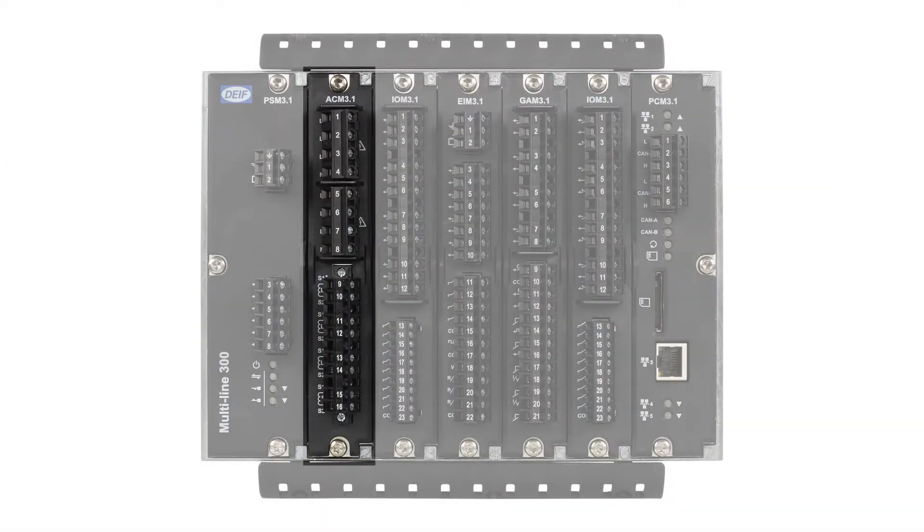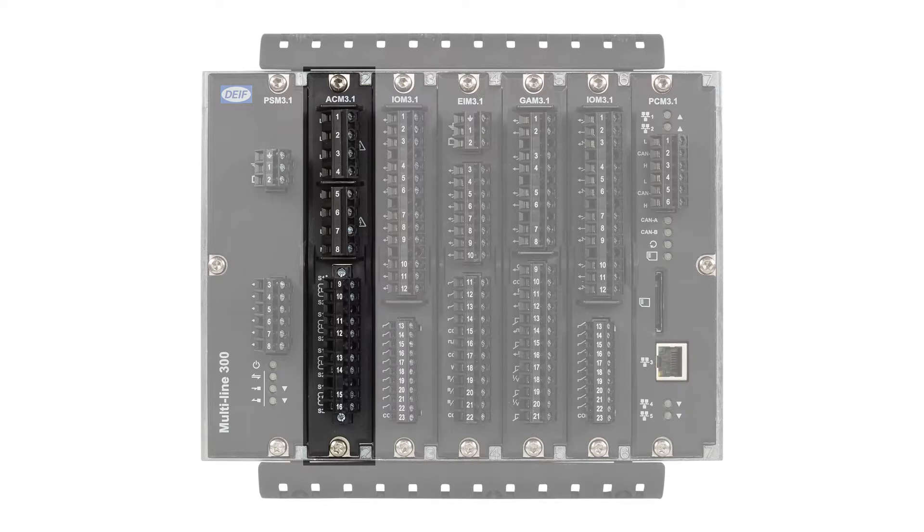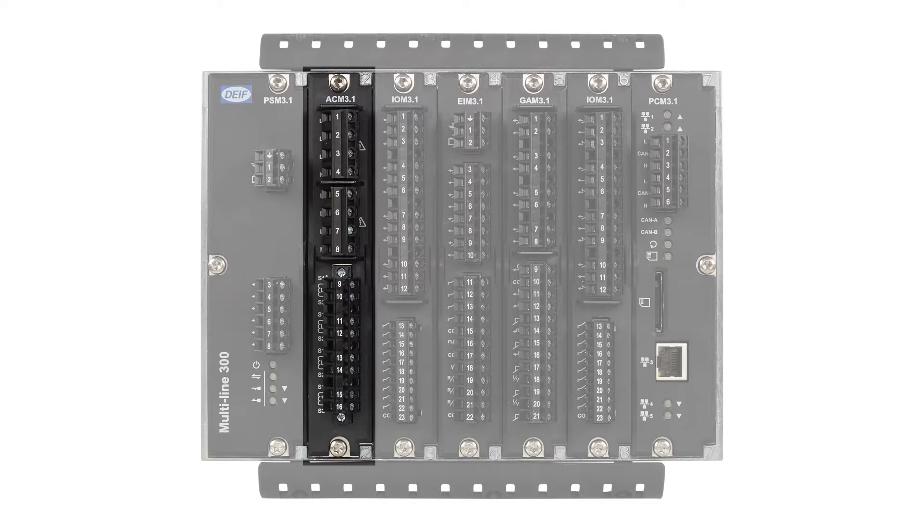The alternating current module ACM 3.1 measures the current and voltage on one side of the breaker and the voltage on the other. The module responds when the measurements exceed the AC protections. It uses the AC measurements to check the synchronization before the breaker closes.